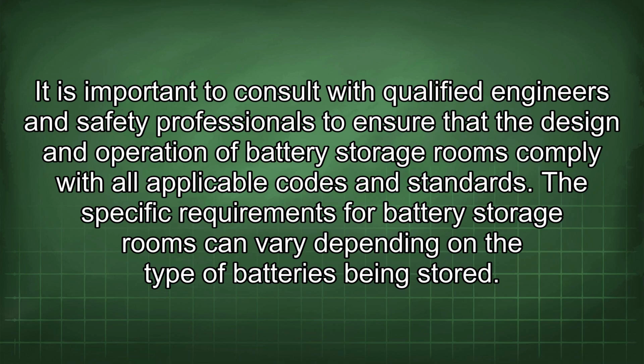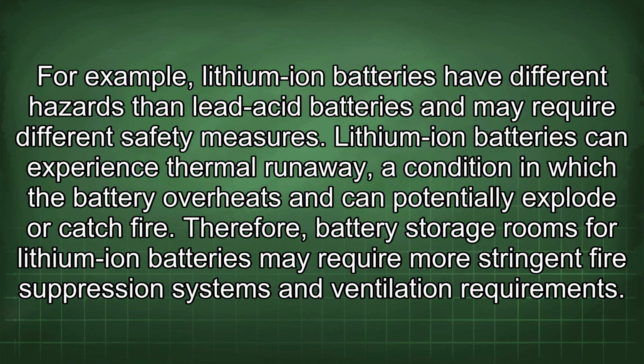The specific requirements for battery storage rooms can vary depending on the type of batteries being stored. For example, lithium-ion batteries have different hazards than lead-acid batteries and may require different safety measures. Lithium-ion batteries can experience thermal runaway, a condition in which the battery overheats and can potentially explode or catch fire. Therefore, battery storage rooms for lithium-ion batteries may require more stringent fire suppression systems and ventilation requirements.